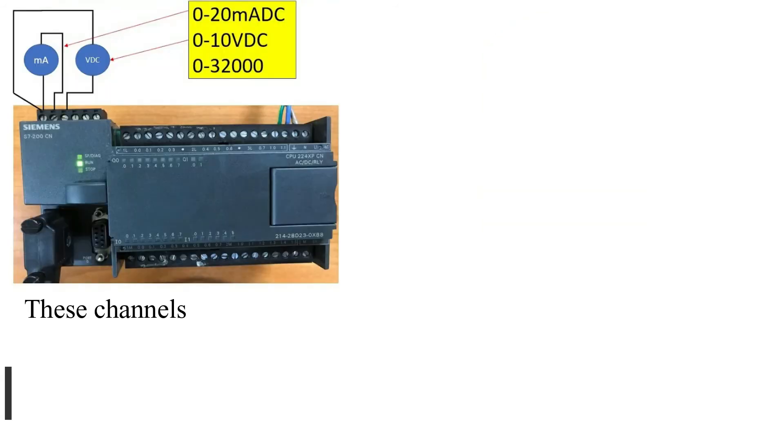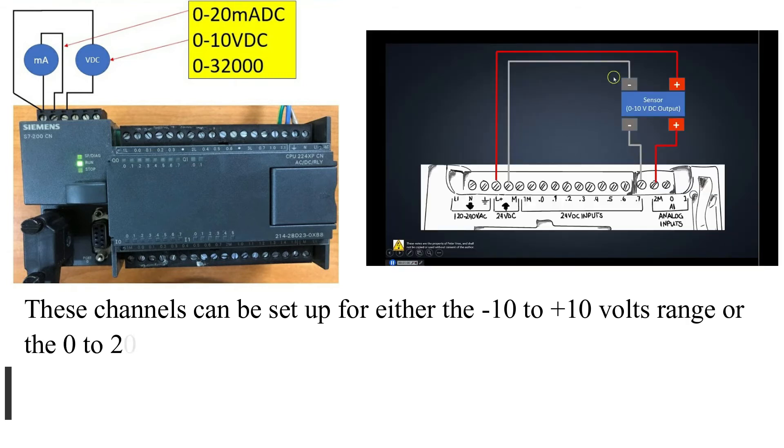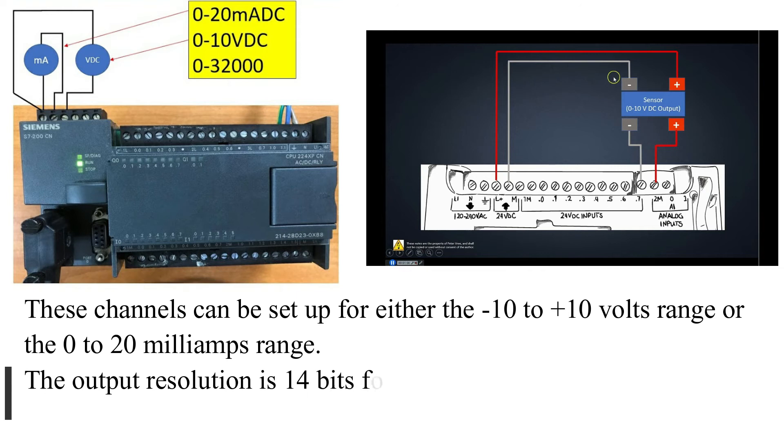These channels can be set up for either the minus 10 to plus 10 volts range or the 0 to 20 milliamps range. The output resolution is 14 bits for the voltage range and 13 bits for the current range.